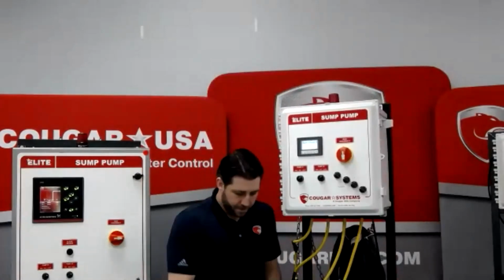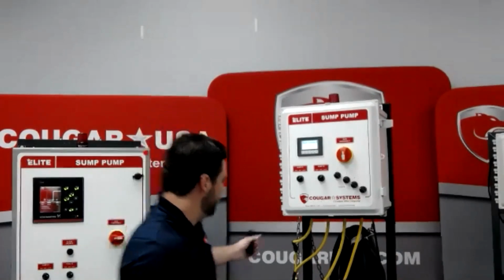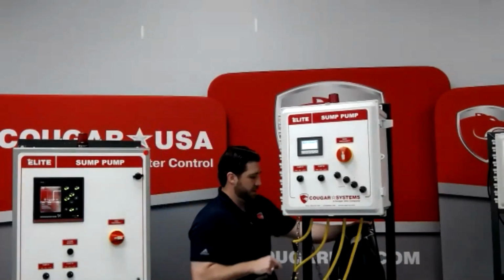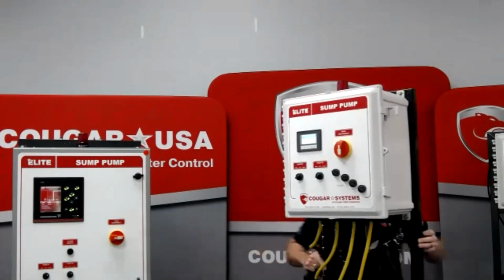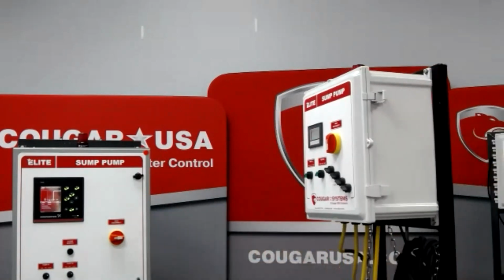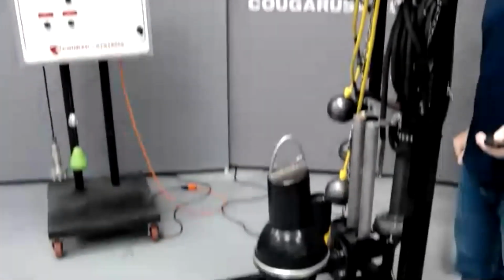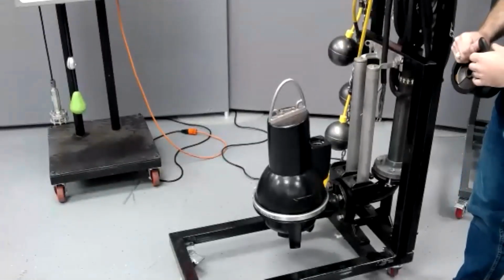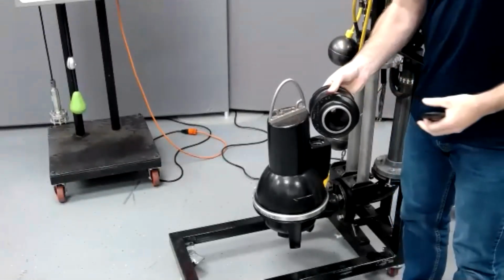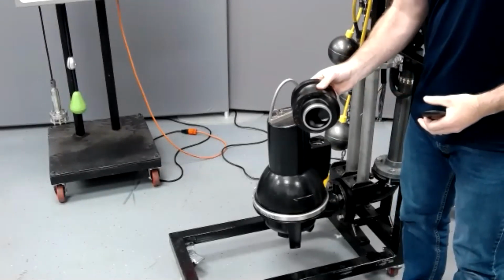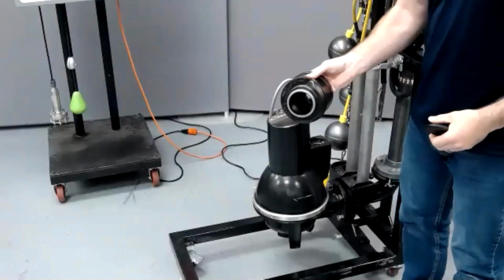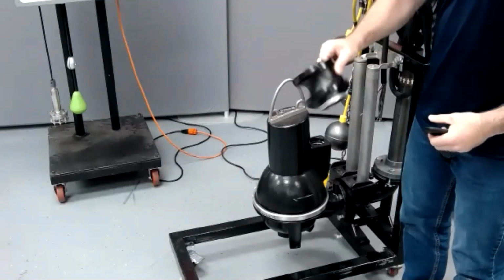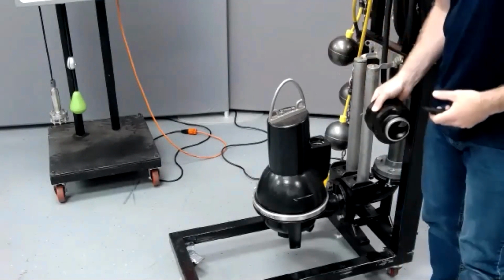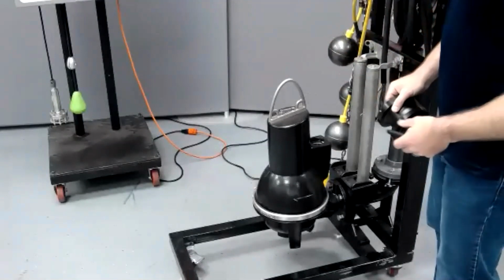CU352. And actually, instead of the 352, I'll show you the SL pump itself. The difference between our SL pump and the SE, or the PIP that we showed you, is that this is going to be a non-clog style pump with an open channel impeller. So the water is actually flowing through this impeller, and it can pass solids. This one up to 2-inch, larger ones up to 4 or 6-inch, depending on the size.